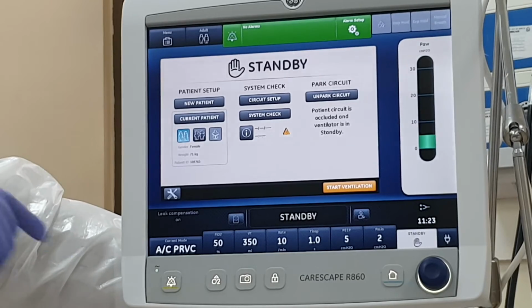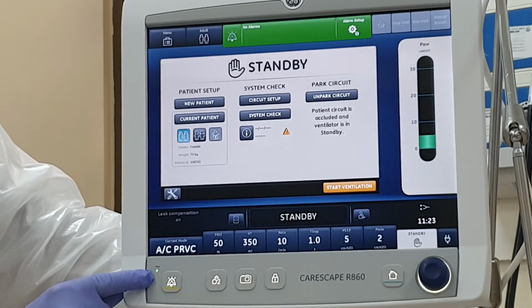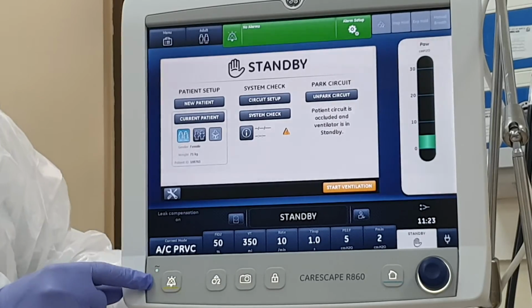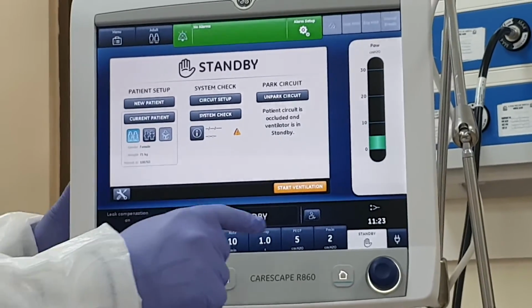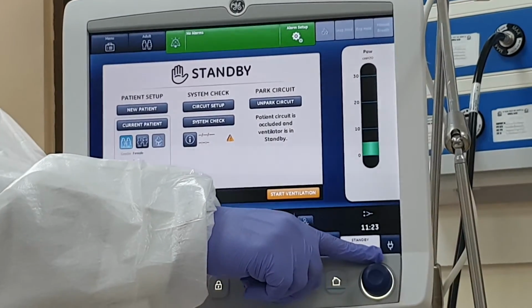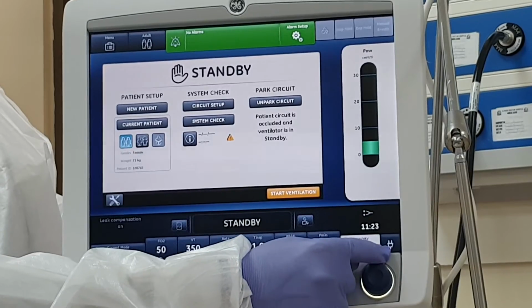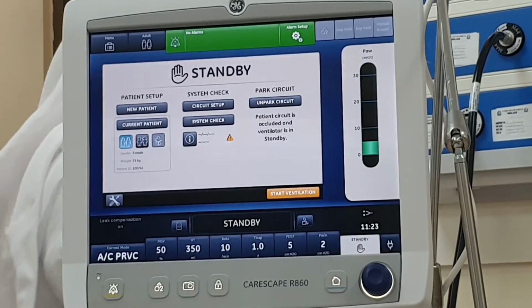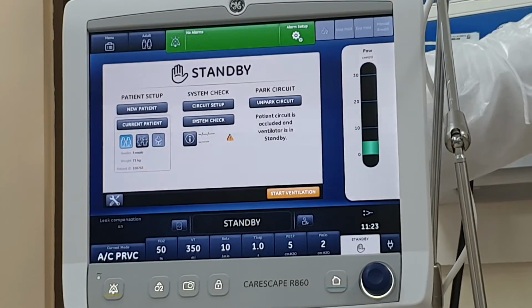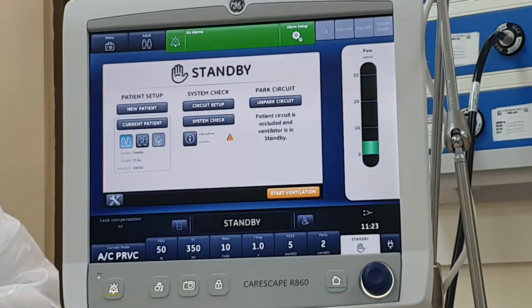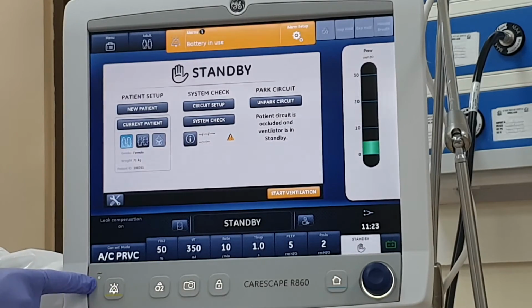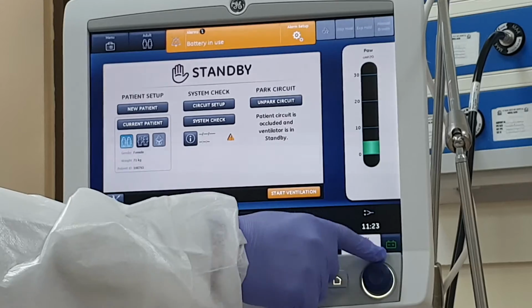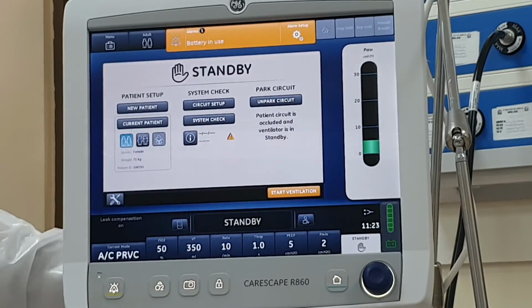Okay, wonderful. This color indicates that it's connected to the electricity. If it's not, then it's going to be off. Another way to know if the ventilator is connected to the electricity or not is the cable over here. If I disconnect it now, what are you going to have? Nothing. This one is going to turn off, and now the battery is on. If you hit the battery, it will show you how many bars you have. The last bar will last for 10 minutes, depending on the rate and tidal volume.